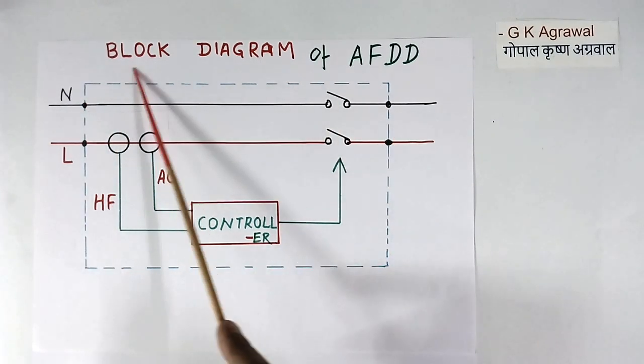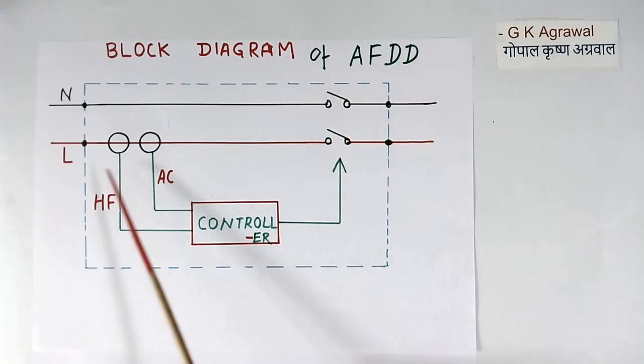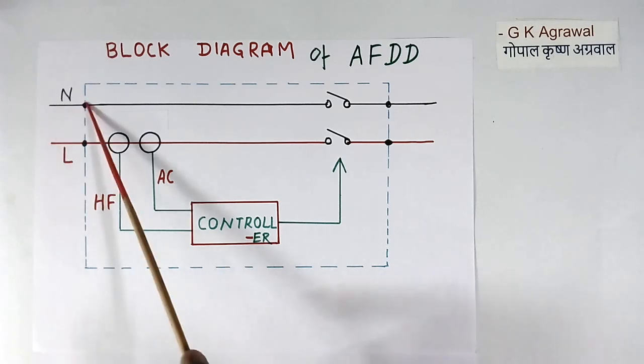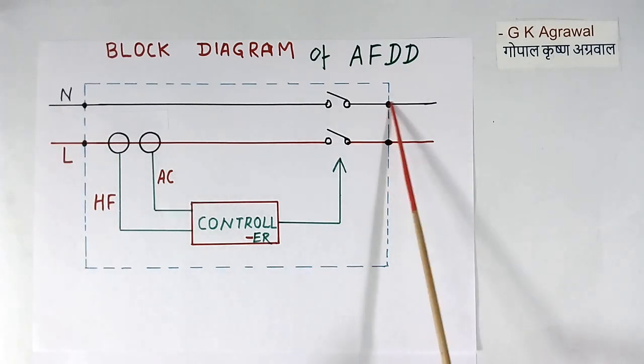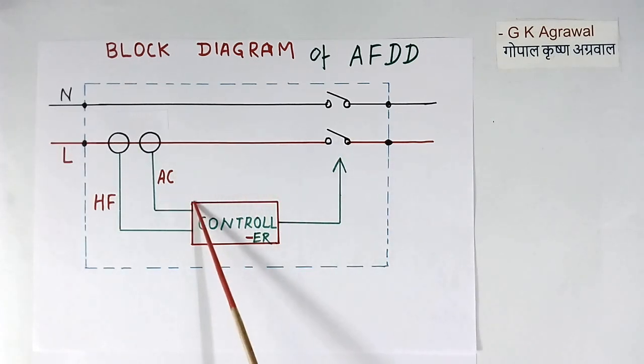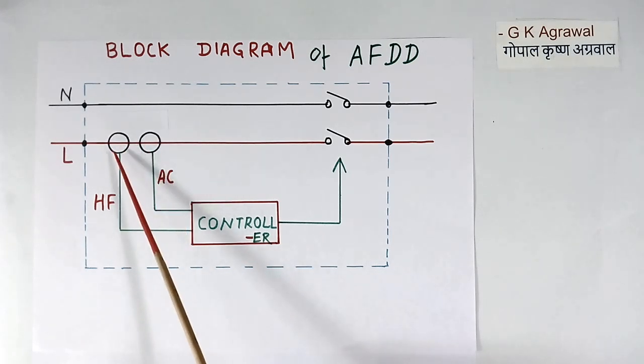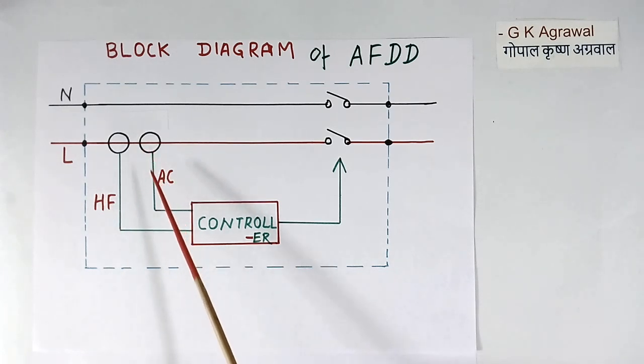This is block diagram of AFDD breaker. See here two wires are coming, line and neutral, and two wires are going out. And current is flowing in this wire. This is controller. This is electronic controller. It has two sensors. One sensor senses the high frequency current. Other sensor senses the low frequency AC current.